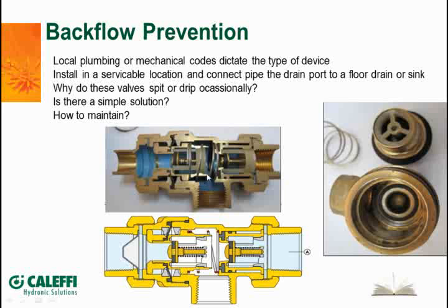It's a piece of Teflon tape. You might see it and be able to pull it out. But you can clean that seal surface there just like you do on a faucet washer on your sink. If you've got a drip, you take it apart, you see there's a particle of dirt or a little stone or a pebble or something stuck in there, and you just take it out, and in most cases it's going to be just fine. So disassemble it right here, pull it apart, clean that seal surface, and you should be back in business. It is union connections on both ends, so it makes it easy to take it apart. As long as you've got a shutoff valve here, you can get this out of the system and get in there and clean it out.